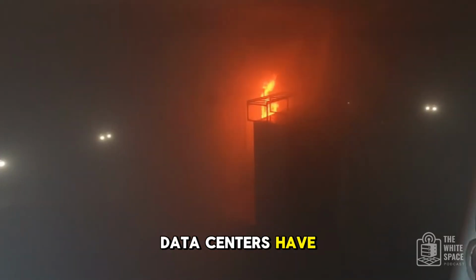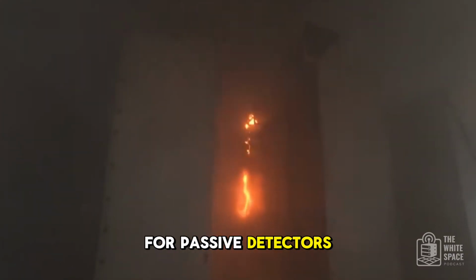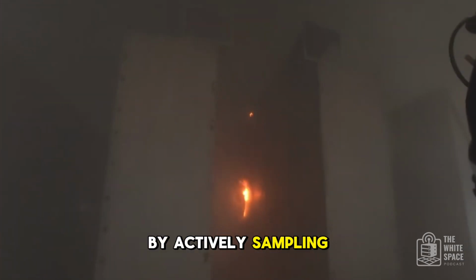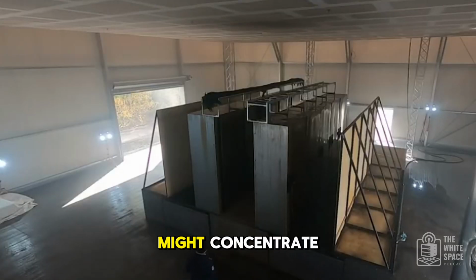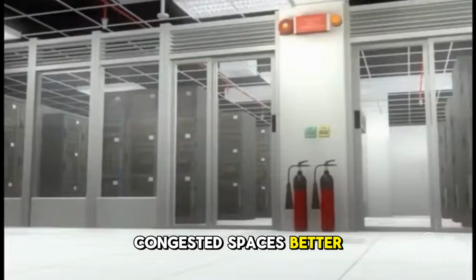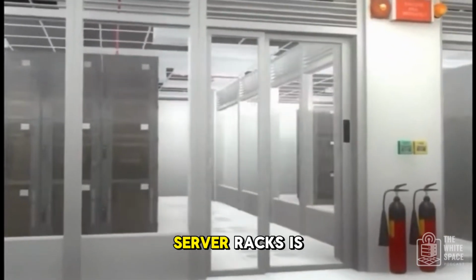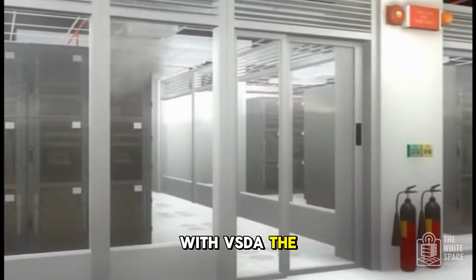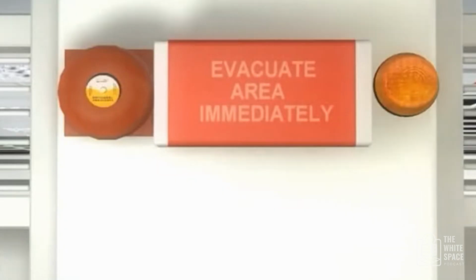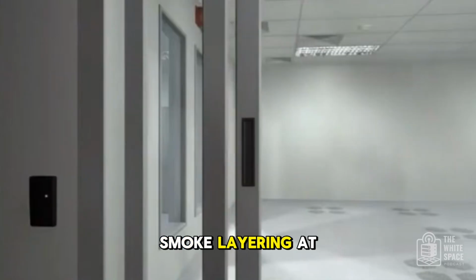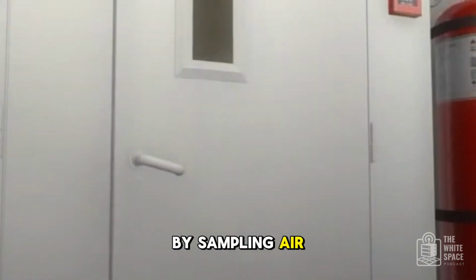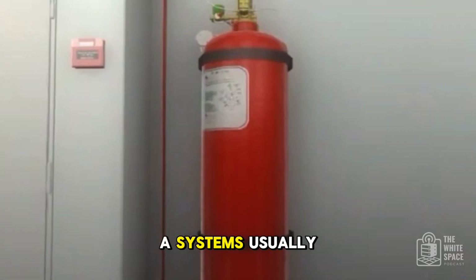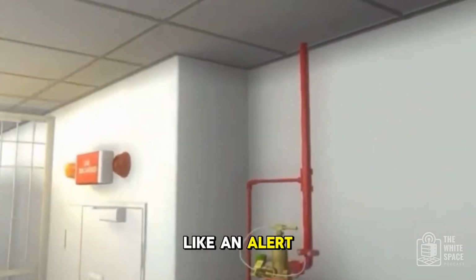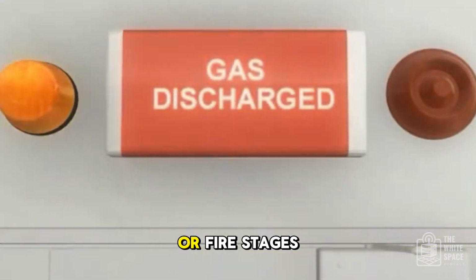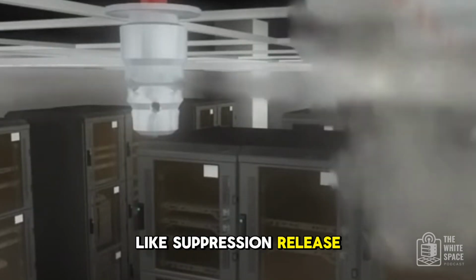That's the goal. Also, data centers have high airflow from cooling systems, right? CRACs, cooling units, fans everywhere. Sure. That airflow can dilute smoke, making it harder for passive detectors to see it quickly. VESDA overcomes this by actively sampling air from multiple points, including return air grills where smoke might concentrate. Wow, clever. It also handles congested spaces better. Maintaining spot detectors buried deep inside server racks is a nightmare. With VESDA, the detection unit is accessible, the pipes do the hard work, and it deals with smoke stratification, smoke layering at different heights due to temperature differences, by sampling air at multiple levels. Okay, that makes sense. Plus, VESDA systems usually have multiple alarm levels, like an alert stage for early investigation, then maybe action or fire stages that trigger more serious responses like suppression release or evacuation.